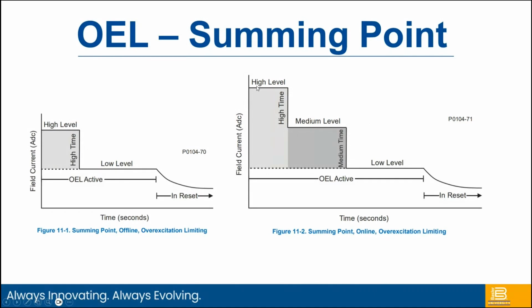The high current level is an instantaneous cap. If you're above the medium level, then after the high time expires, it will pull excitation down to the medium level for the duration of the medium time. And then there is an integrating reset condition that occurs after you come off or drop excitation below the low level. Because of that field winding heating, you don't want to go immediately back to the starting place. If you exceeded the low level threshold again, you want to go to some advanced period of time based upon how long it's been in reset. So that is essentially the summing point style of OEL.